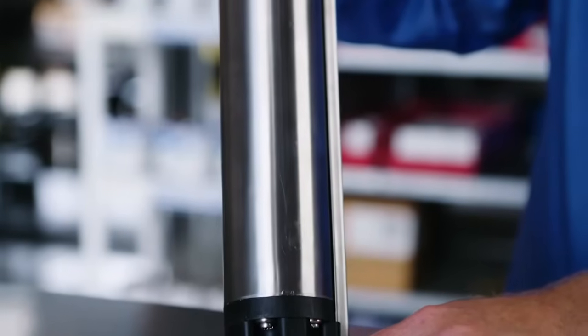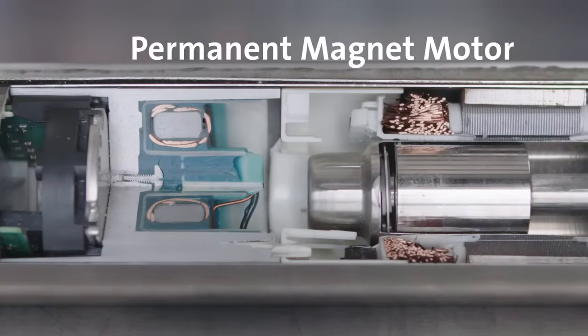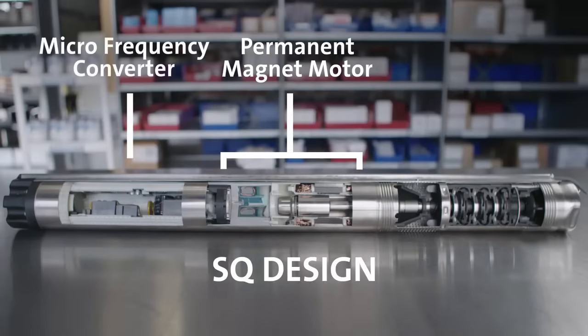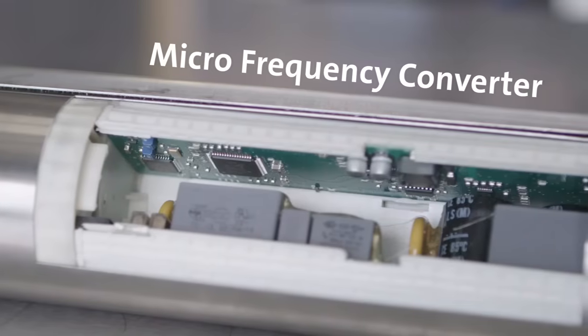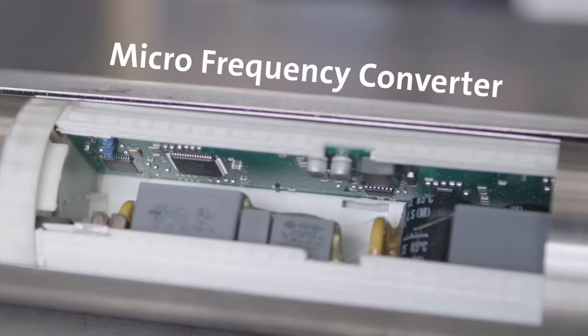The Grundfos SQ is ideal for small or restricted wells, and also has a range of features that makes it a great choice for all residential water well systems and irrigation. The SQ pump features a stainless steel pump housing and a highly efficient electronically controlled permanent magnet motor. The motor runs at 10,700 RPM on single phase power with a simple two-wire design. The SQ's built-in micro frequency converter changes the single phase input power into three-phase power supply, making the SQ motor operate as effectively as a conventional three-wire motor design.